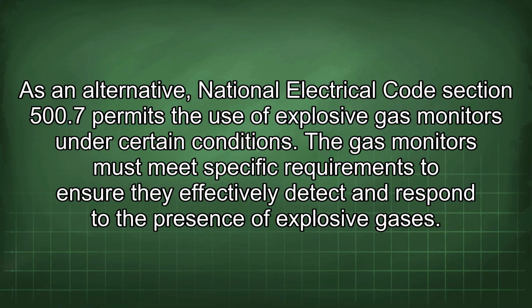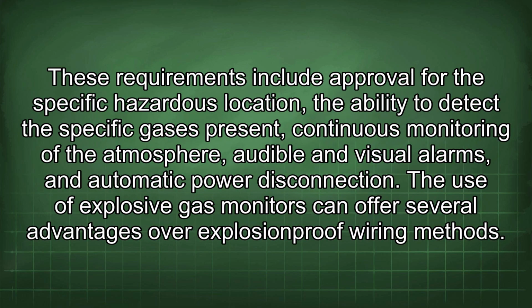The gas monitors must meet specific requirements to ensure they effectively detect and respond to the presence of explosive gases. These requirements include approval for the specific hazardous location, the ability to detect the specific gases present, continuous monitoring of the atmosphere, audible and visual alarms, and automatic power disconnection.